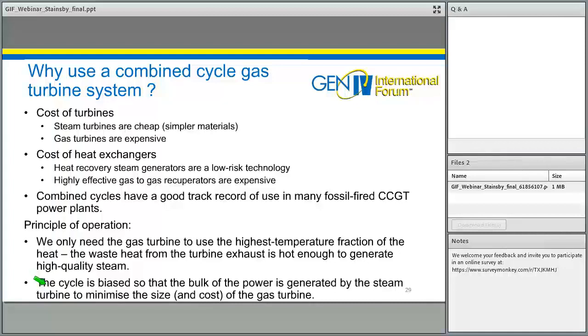Heat exchangers are quite expensive items, but heat recovery steam generators are well established and a low risk technology, and highly effective gas-to-gas recuperators, the sort needed for a closed cycle gas turbine, are very expensive to achieve the high effectiveness we need. Combined cycles have a good track record, many years of experience now in the fossil fuel combined cycle gas turbine industry.